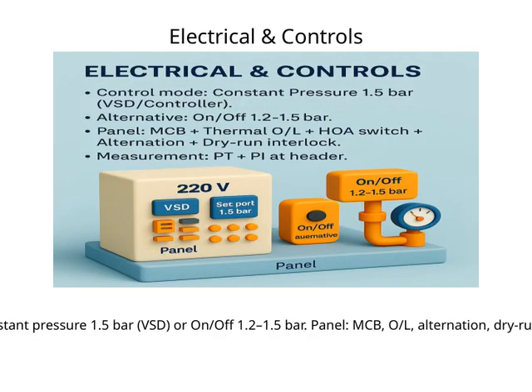Let's take a look at the electrical and controls section. Here, the system can operate in different modes depending on the application. For example, it can run in a constant pressure mode at 1.5 bar when using the VSD, or in an on-off mode within the range of 1.2 to 1.5 bar. This flexibility helps optimize performance based on demand. The control panel is equipped with essential safety and control features. It includes a miniature circuit breaker, or MCB, to protect against overloads and short circuits. There's also an overload protection device, or OL, to prevent damage from excessive current. Additionally, the panel features alternation, which ensures even wear and tear by switching the operational cycle between components.